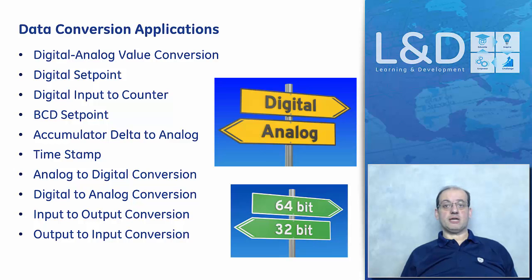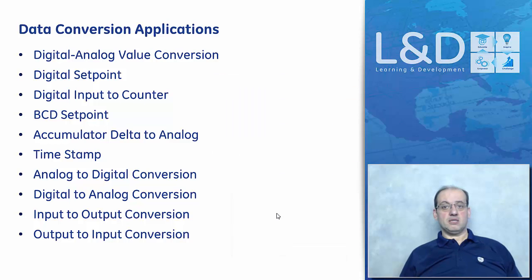For example, you've got two remote masters and you want the digital input sent from one master to translate into an output to the other master. A good example is what we call a mailbox, where the substation is acting as a mailbox between two remote masters. Let's say one is a transmission and one is a distribution, and they want to tell each other that they've got control. So the transmission will send a digital input to the substation that's picked up as a digital output to the other master, telling the other master, you're not in control of these points, and now the transmission management system is in control.